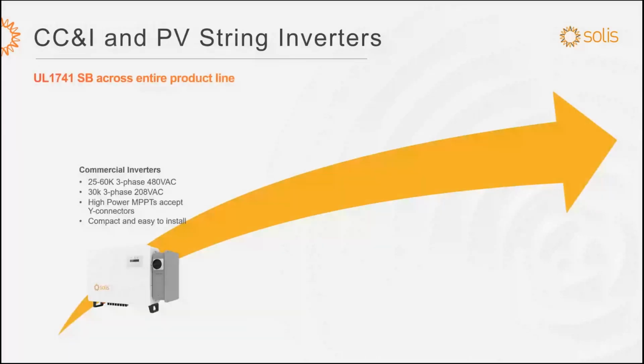So now let's talk about the Solis three-phase inverter line. It starts with our commercial inverters, the smallest one being the 25 to 60 kilowatt platform. Those are 1000 volt DC, 480 volt AC. And that line also has a 30 kilowatt 208 inverter if you have 208 sites. The inverters have lots of MPPTs that could also accept Y connectors, and you'll see some slides coming up on what they look like. So very compact, easy to install, and that's for rooftop type projects.